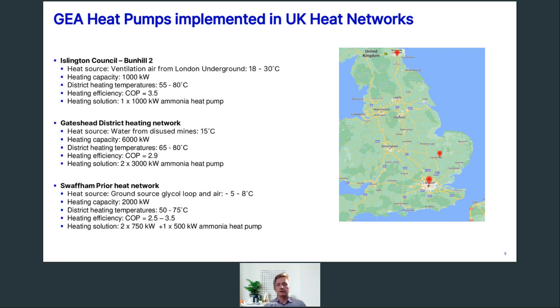This is the 2 times 3 megawatt system. It's a total of 4 compressors, because it's a 2-stage system - we need to lift the temperature all the way down from around 7 degrees as the water cools, and heat the water up to 80 degrees. On the right side, you can see the plate and frame heat exchanger.